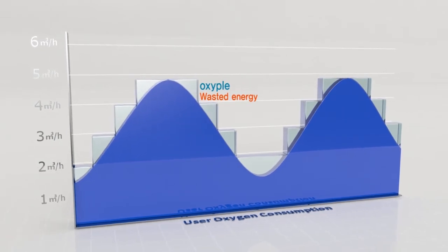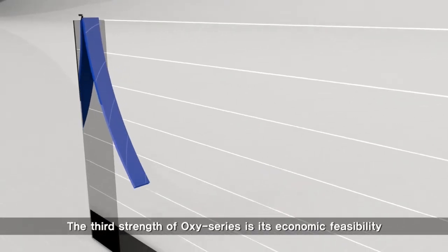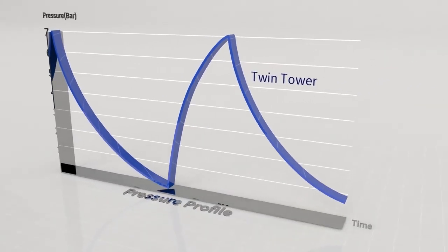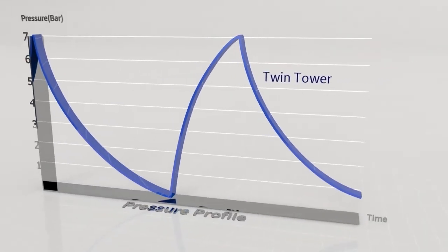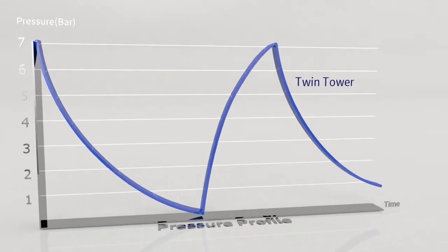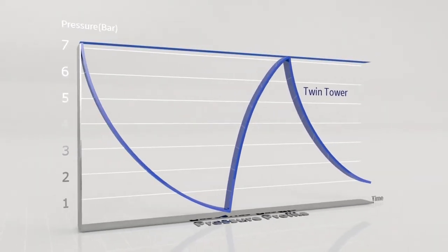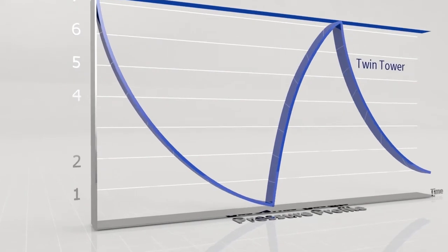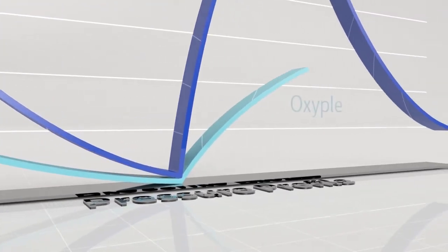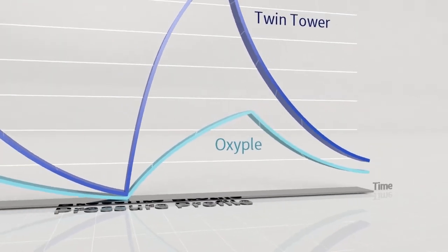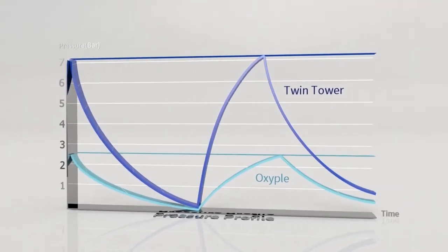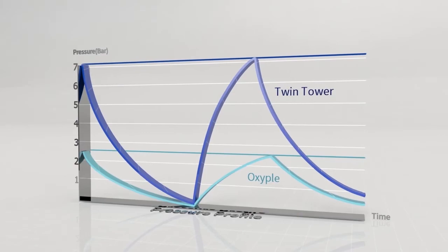The third strength of the Oxy series is its economic feasibility. Previous products using twin tower methods perform the PSA process at seven to eight bar, thus requiring compressed air over eight bar. On the other hand, the Oxypole performs the PSA process at a pressure of 2.5 bar, requiring only about three bar of compressed air.